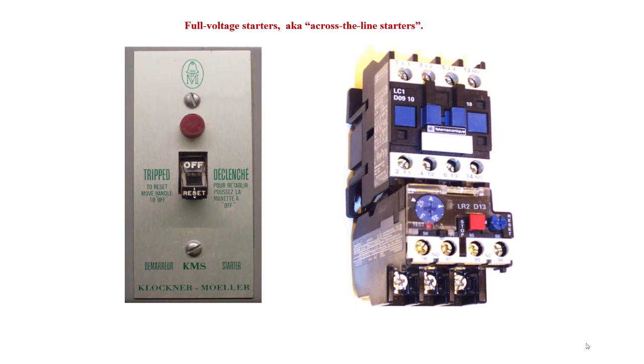So when we're talking about starters, there's two types of across the line or full voltage starters that you're probably familiar with. One of them is our manual motor starter, which is on your left hand side of the screen, and the other one is your magnetic motor starter. One of the things that these will have is overload devices in them, and these are across the line or full voltage starters. That means when we energize the coil, or if I flip that switch, the motors are going to see full voltage to the motor terminals at that moment. So for the most part, that's fine.